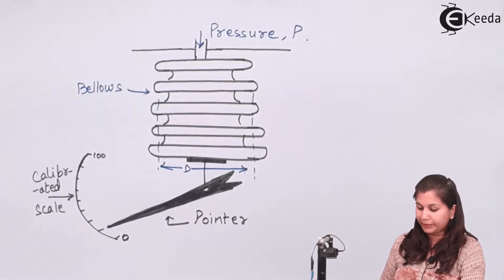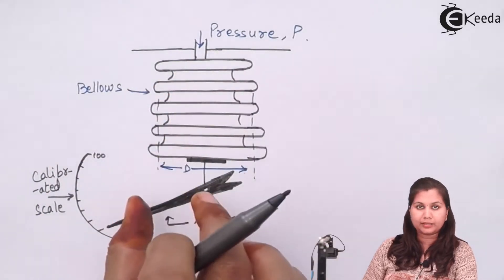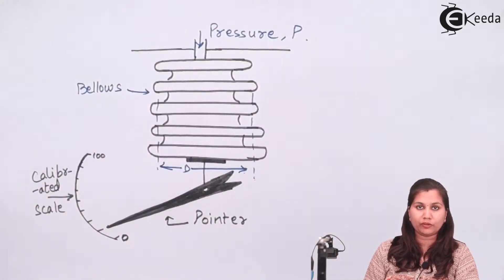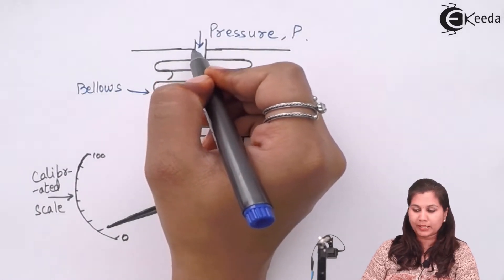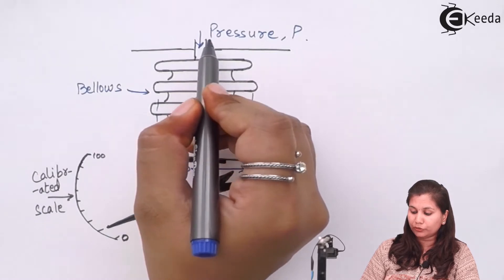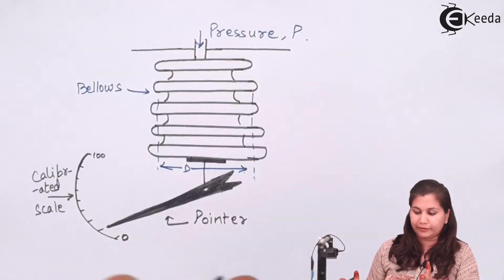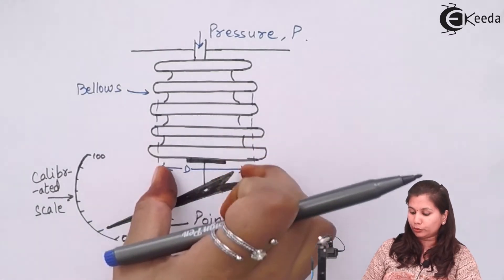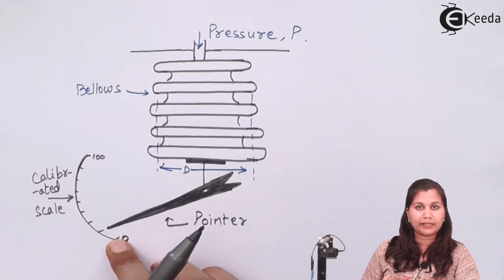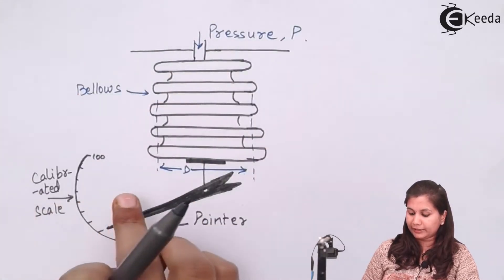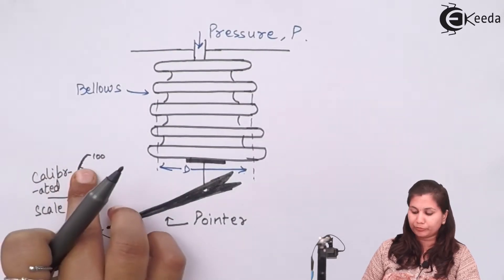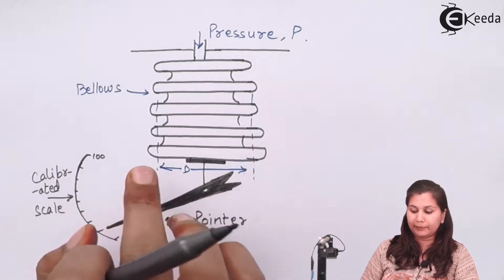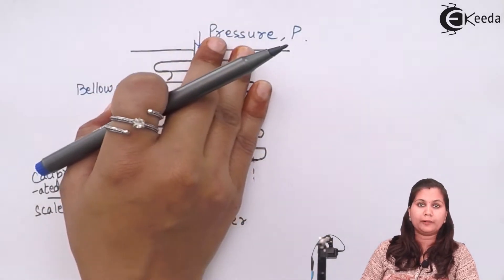So this is a bellow. Here you can see that it consists of circular parts which are joined together one over the other. When the fluid whose pressure we want to measure is allowed to enter from the top side into the bellows, it is going to expand axially in this direction, and due to this expansion the pointer is going to move over the calibrated scale. So pressure can be directly measured by taking a reading from the scale. This scale is calibrated in terms of pressure, so the expansion and contraction of this bellow element is directly proportional to the pressure of the fluid.